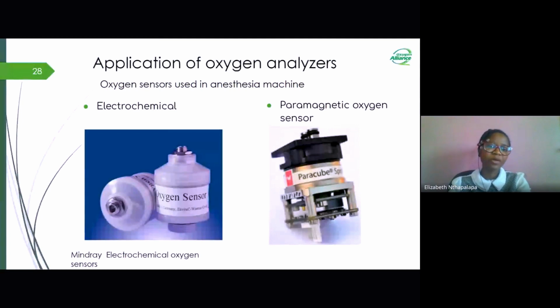To your left, we have the electrochemical oxygen sensors. Specifically, these ones are for the Mindray anesthesia machines, and they give the mean oxygen concentration of the breathing circuit. While to your right, we have the paramagnetic oxygen sensor. This one is for the ParaCube, and it is also used to give the oxygen concentration in the breathing circuit. We can say that paramagnetic oxygen sensors have a sufficiently rapid response time to measure both the inspired and end tidal levels in the breathing circuits.